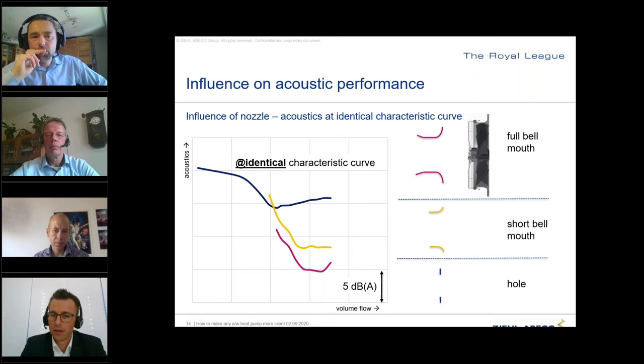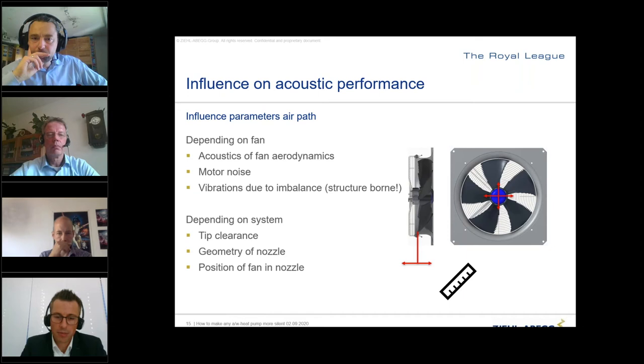So the most critical thing is to put a full bell mouth, or a very good inflow situation, to the fan, which can be guaranteed by a very good and high quality nozzle. Another system-dependent parameter is, of course, the position of the fan in the nozzle. It has to be positioned in axial direction and radial direction in the correct way. I think this is quite clear.